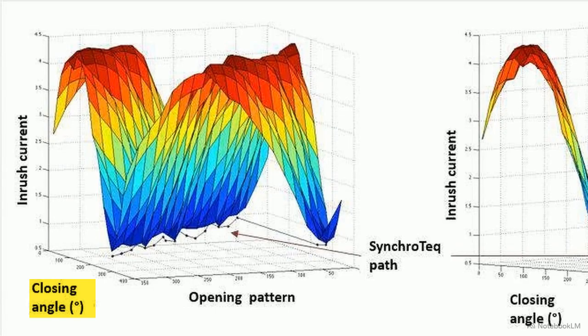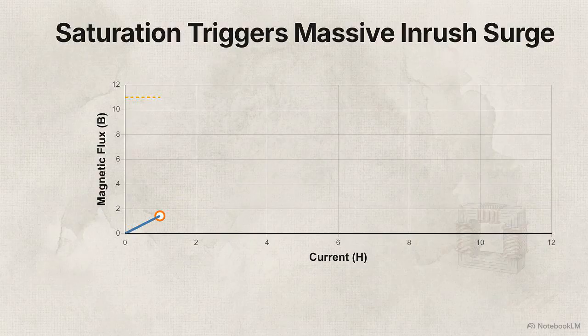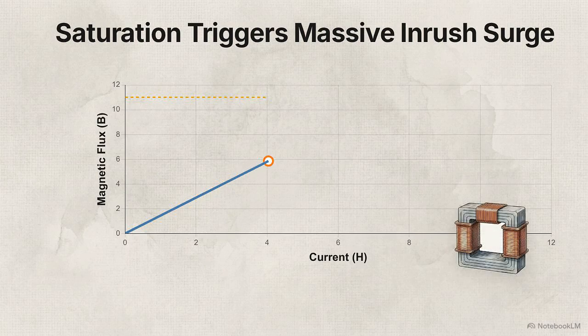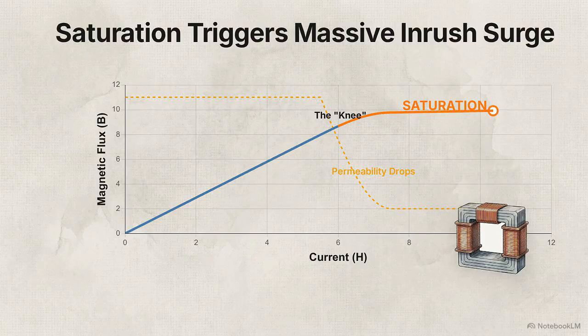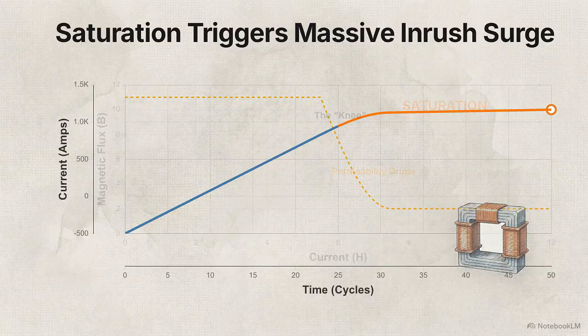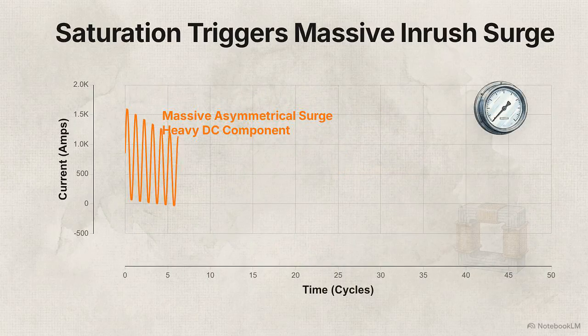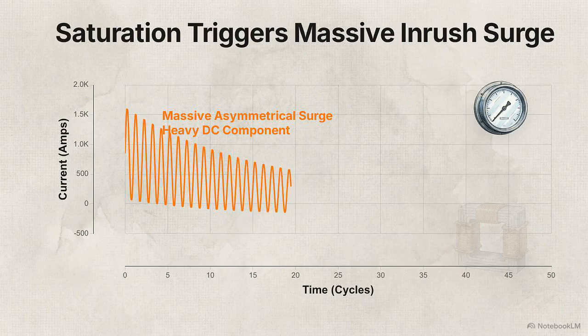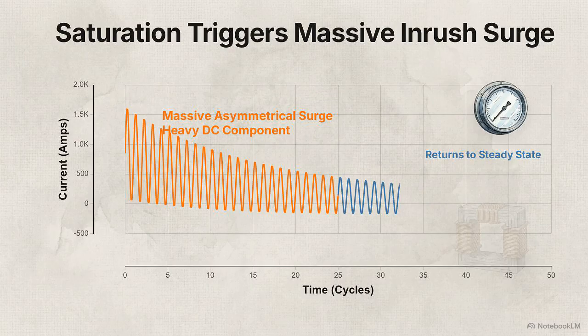and the closing angle. The worst-case scenario occurs when the breaker closes where the newly applied flux pushes exactly in the same direction. When those two forces compound, the total flux breaches the knee of the BH curve. The core physically cannot hold any more magnetic flux. It enters saturation. In this saturated state, the core's relative permeability drops off sharply. The magnetizing impedance collapses, and the transformer pulls a massive surge of current from the grid to maintain the required flux. Because of the initial flux offset, this surge is highly asymmetrical, often carrying a heavy DC component that can linger for tens of cycles before returning to a steady state.